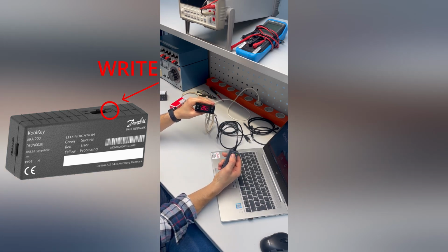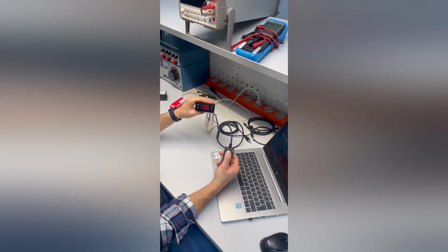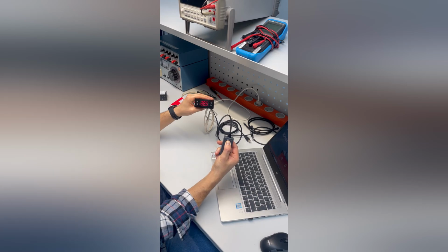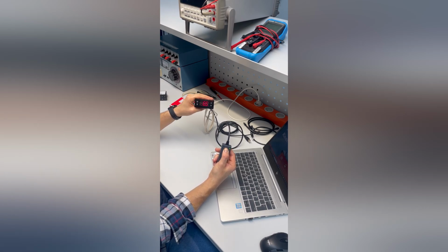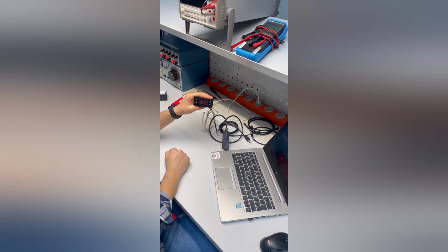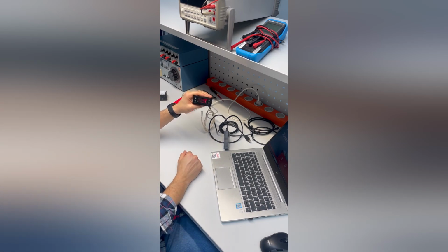And let's follow it here with the ERC. I will press the button now. And the KoolKey will recognize that the device connected is associated with the database saved here inside the KoolKey. So the download process is automatic. And let's wait for a couple of moments so it can restart. Okay, and let's take a look at the set point. And here it is, 15 degrees, just like the database that we have saved. So that's how you use the KoolKey and the MPK.